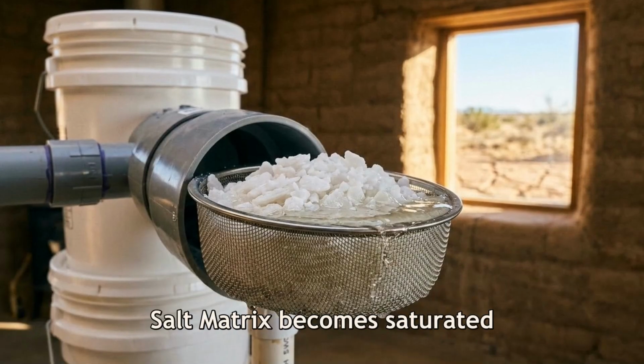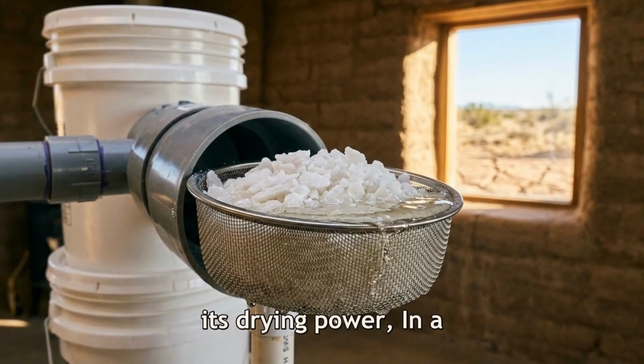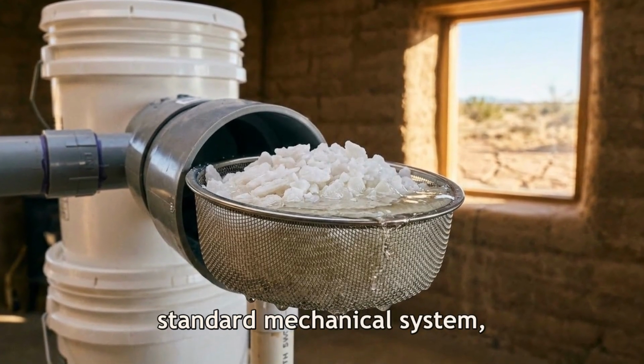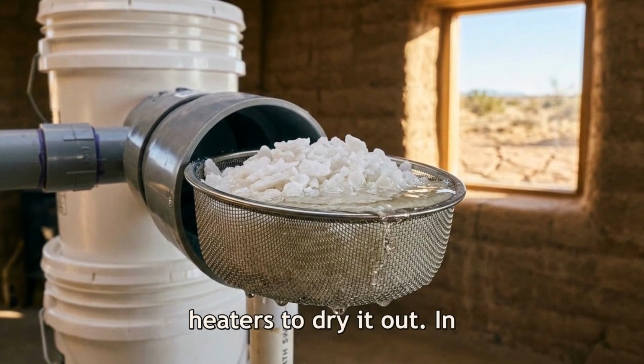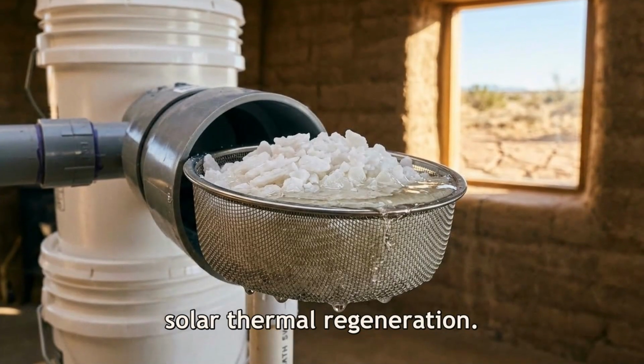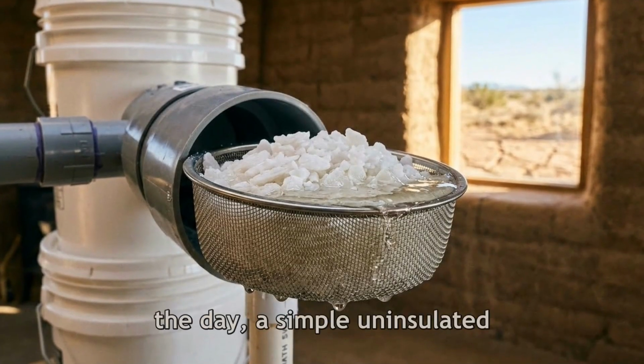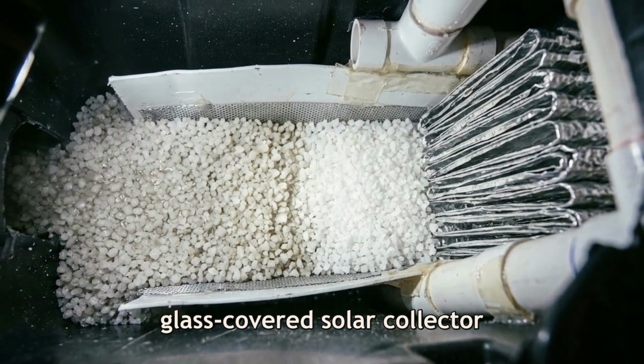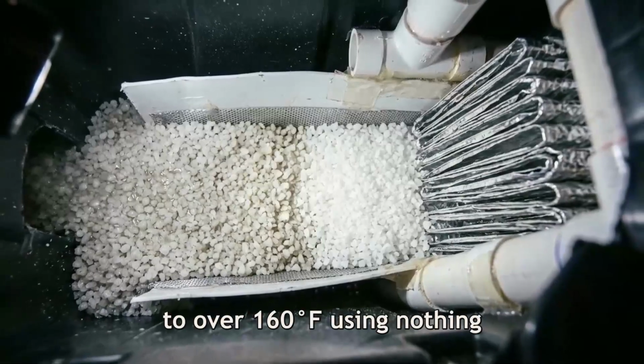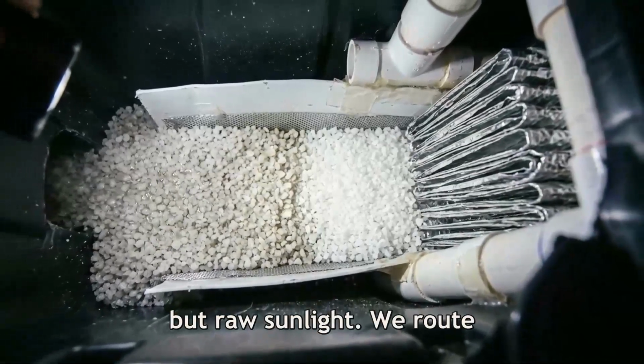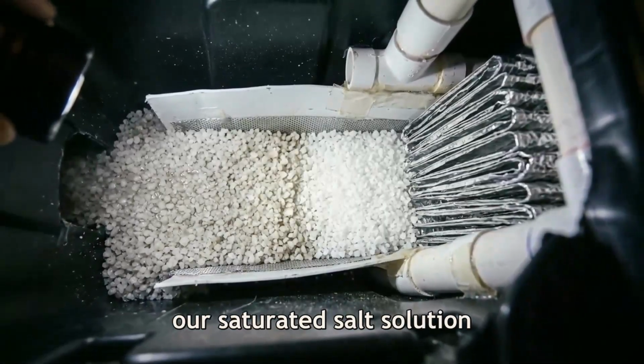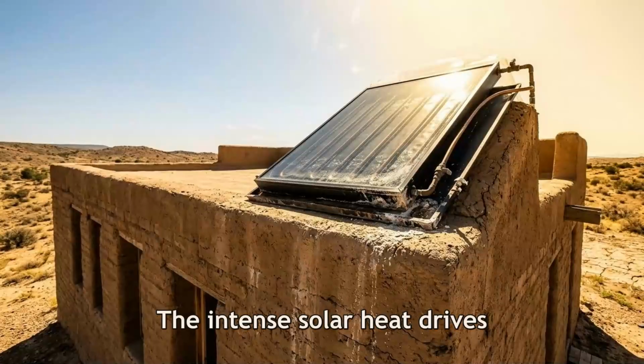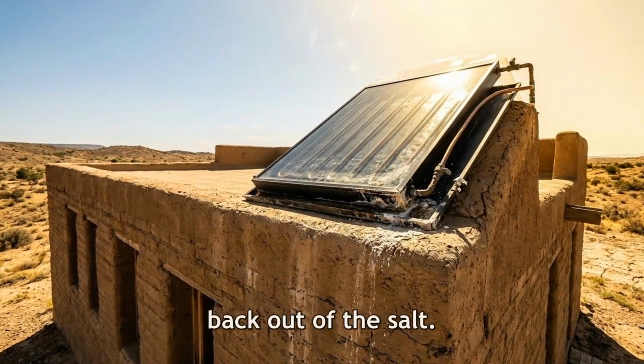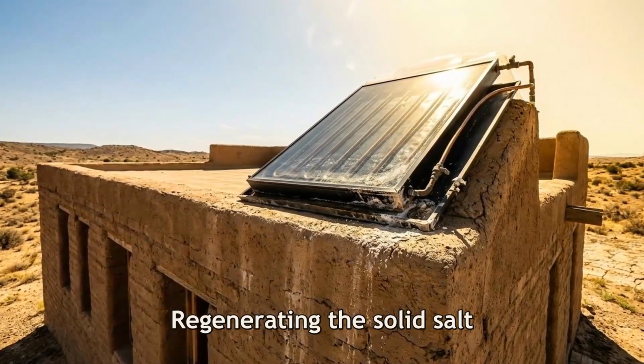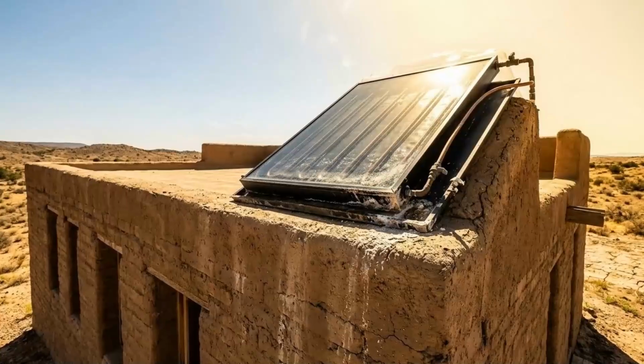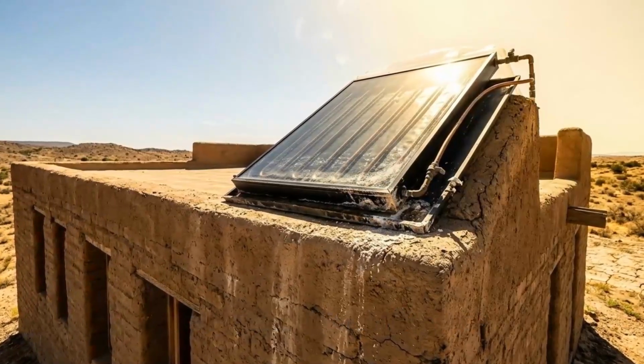Eventually, the salt matrix becomes saturated with water and loses its drying power. In a standard mechanical system, you would need electric heaters to dry it out. In our passive design, we utilize solar thermal regeneration. During the hottest hours of the day, a simple uninsulated glass-covered solar collector on the roof heats up to over 160 Fahrenheit using nothing but raw sunlight. We route our saturated salt solution through this solar collector. The intense solar heat drives the captured water right back out of the salt, regenerating the solid salt crystals or highly concentrated brine, storing that chemical drying potential for the next cooling cycle.